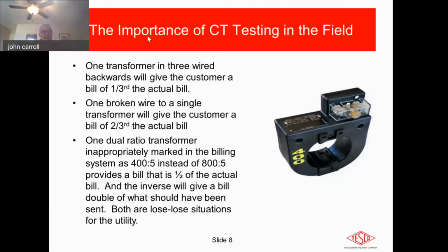Basically what we have here is a transformer and a three-wire circuit. As you can see, if it's wired backwards, you will give a customer a bill of only one third of the actual bill. So that's a 66% reduction. That's significant, even on one phase, even with a low current. With one broken wire, we might get a customer who in actual fact has a bill of two thirds of the actual bill. And remember, this could have been going on since the day they were installed if they were never tested. It's a difficult thing to do at times.